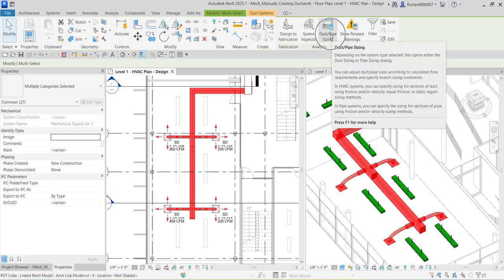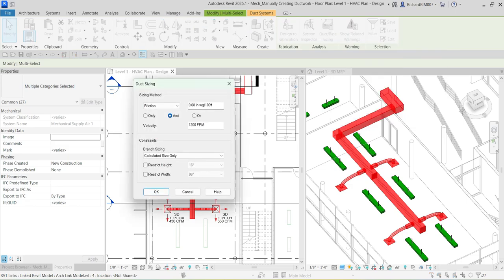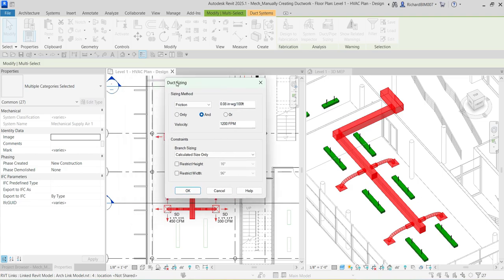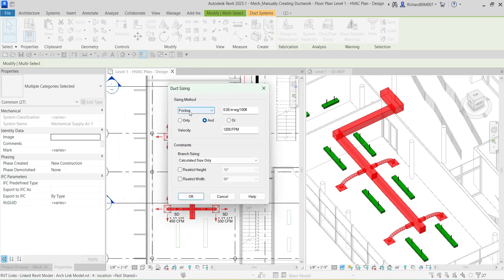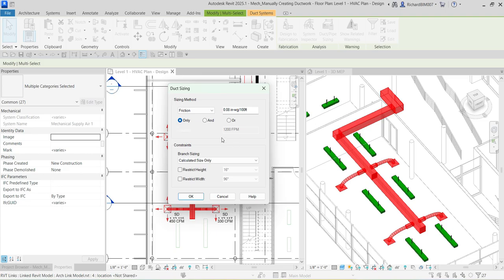Once the duct network is selected, click 'Duct/Pipe Sizing.' In the sizing dialog, you can select your friction settings and velocity. I want to design based on friction using these settings. I'll uncheck 'Restrict Height' since I'm not working in a restricted space like a plenum. I'll use 'Branch Sizing: Calculated Size Only' and click OK.